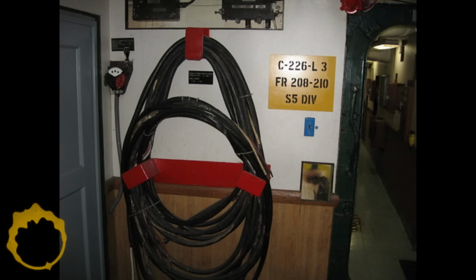You see, basically every major quote-unquote source of power on a warship, whether it's a switchboard or a specific control panel, or just a random bulkhead, and we'll get to why that's just totally weird in just a second, has one of these casualty power risers either on it or connected to it and run somewhere else. So that's the first leg of our patchwork. But the power source only goes to the terminal. It's a disjoint system. Well, that's because around the terminals are wrapped extension cords.